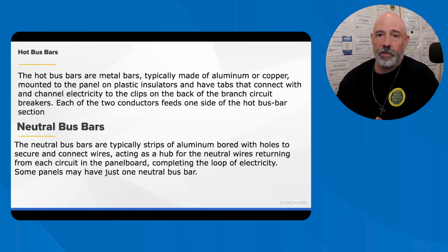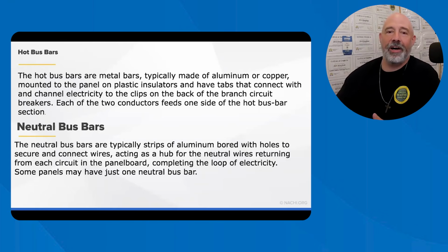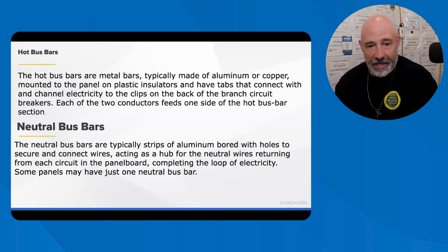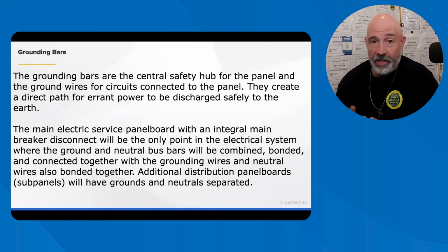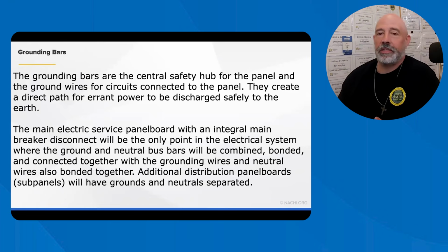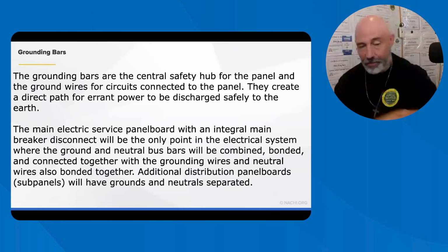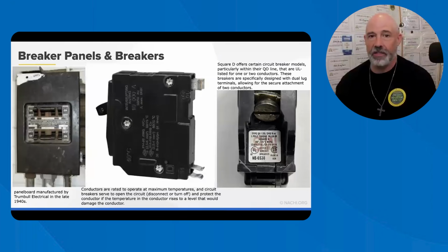The neutral bus bars are typically strips of aluminum bored with holes to secure the connected wires, acting as the hub for the neutral wires returning from each circuit in the panel board, completing the loop of electricity. So it's going like this. Some panels may have just one neutral bus bar. Just saying, okay? Mine in my house has that. The ground bus bar serves as the central point of the grounding system. The main service panel is the only place where the grounds and neutral are bonded together. You've heard me say that all subpanels are separated. They're getting divorced. They can't be together.